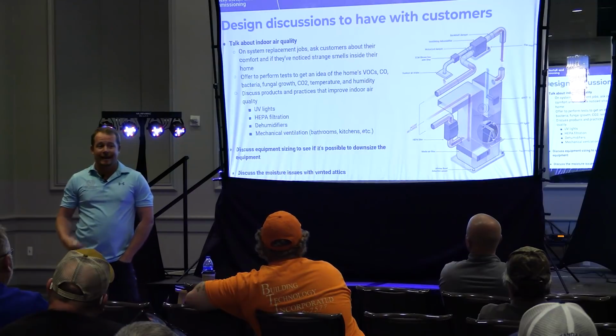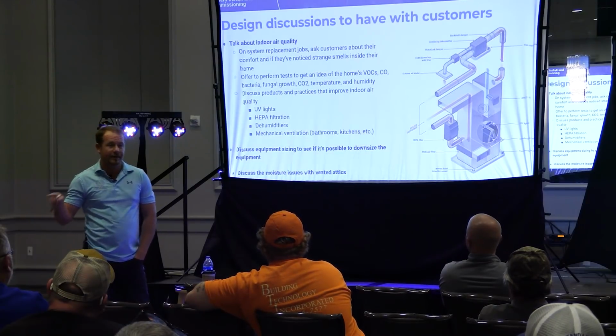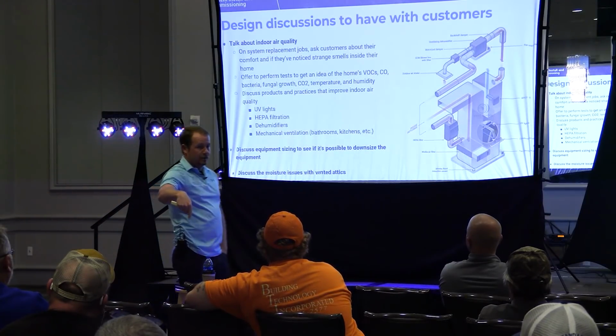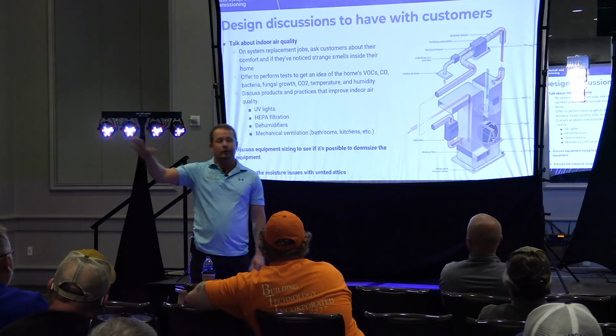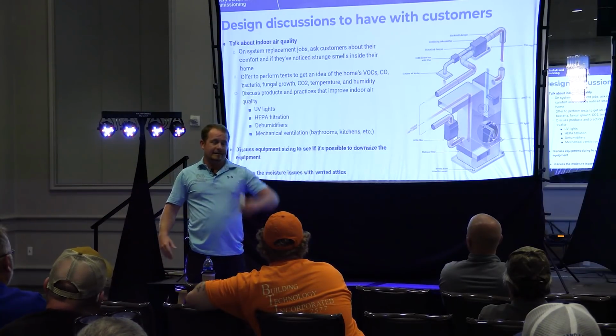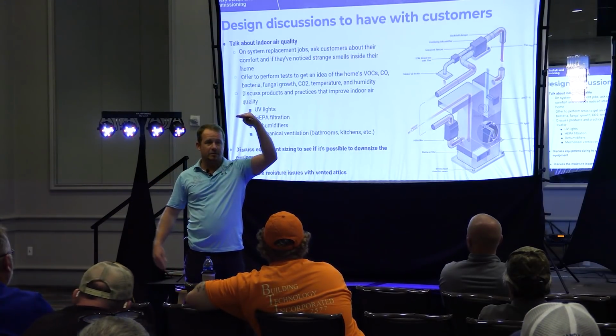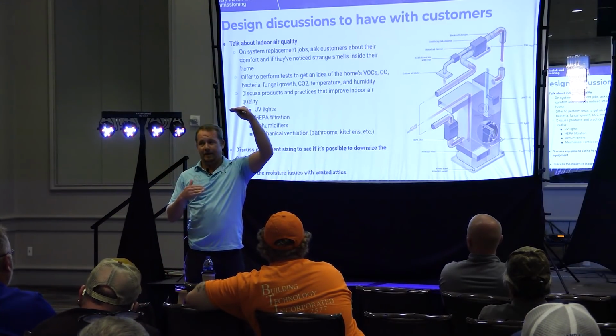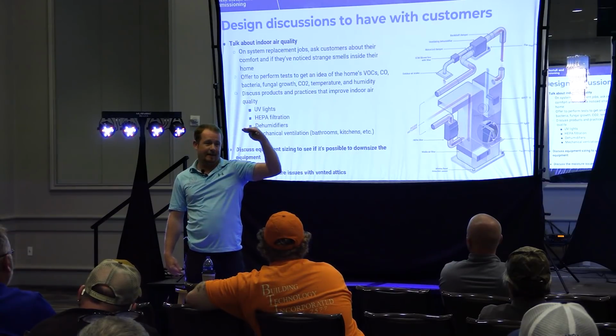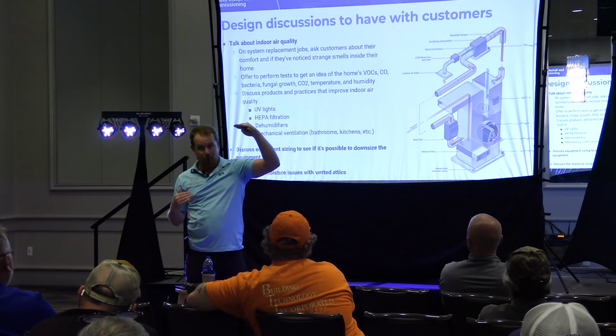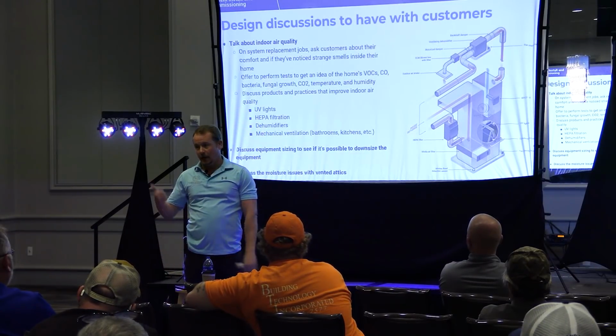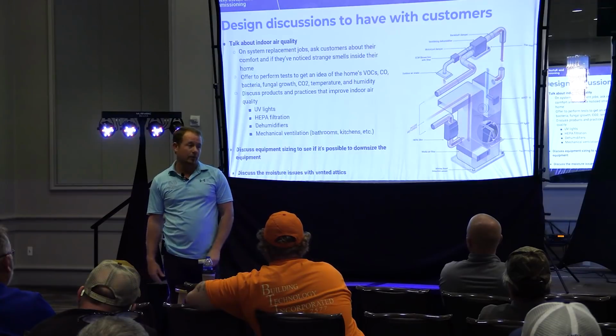Similar things happen and are much more prone to happen in houses where they set the temperature lower. Because if you have a 20-degree delta T and it's 75 degrees inside, what's the supply air temperature? 55. If they keep it 68 inside the house, what's the supply air temperature? 48. That means ducts and everything will be more prone to sweat.